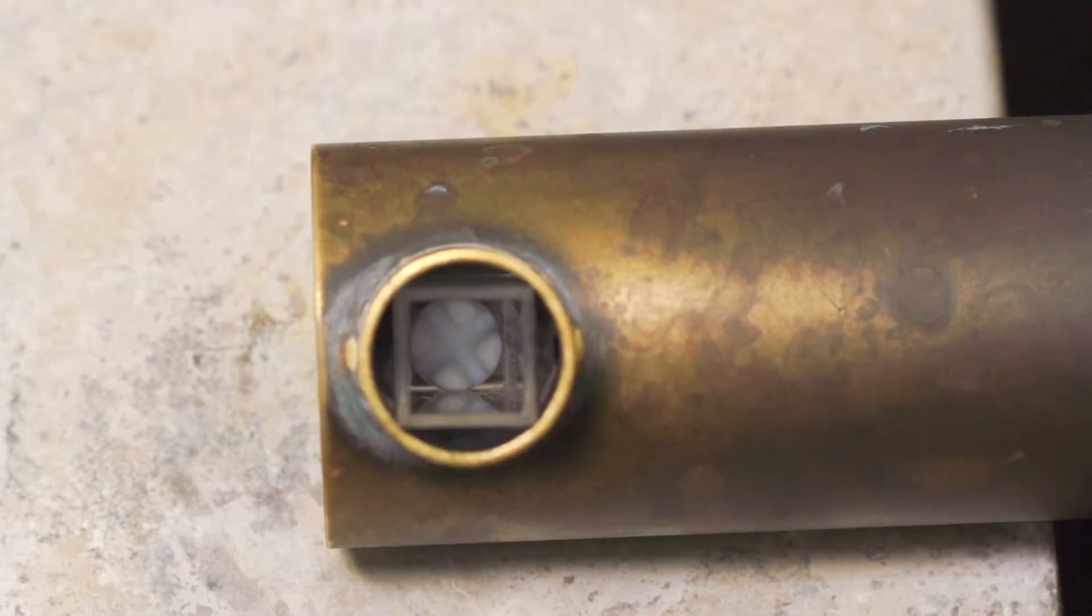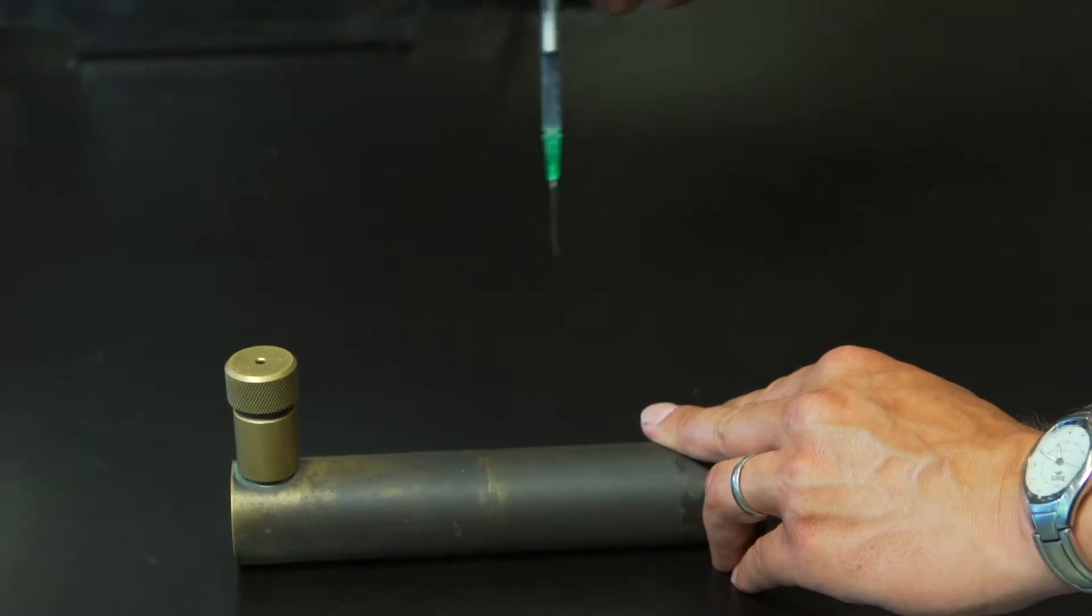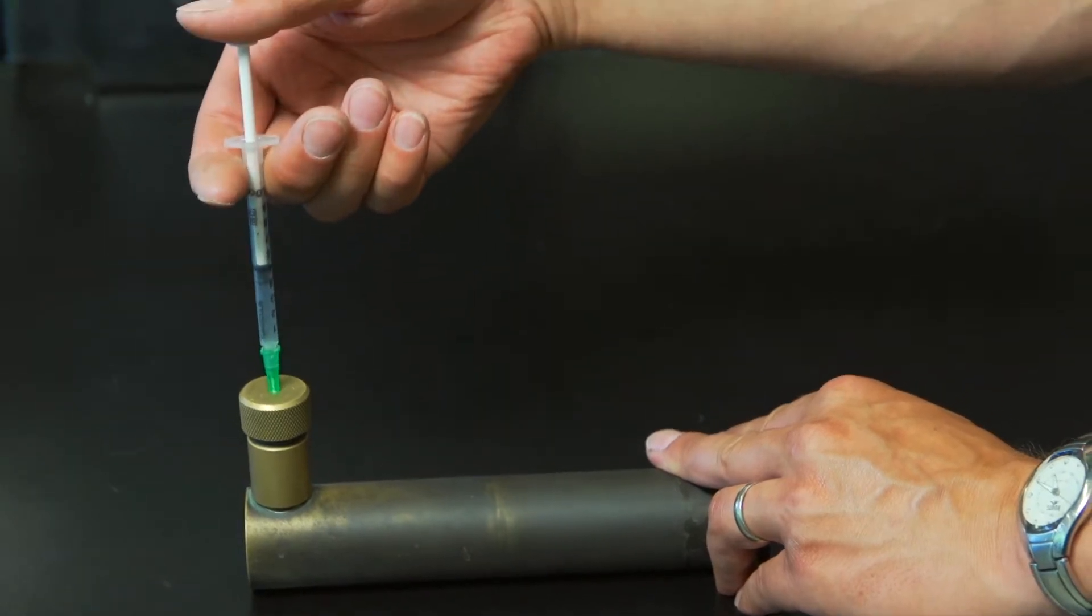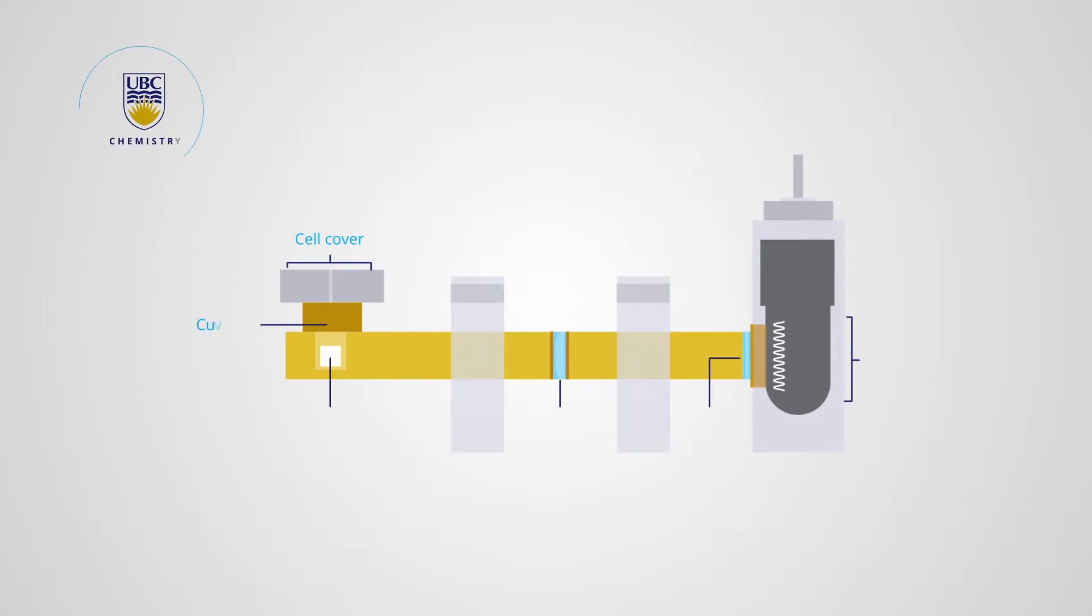Two of the three reagents, hydrogen peroxide and luminol, are pre-mixed here. Your sample is injected into the cuvette through this small opening in the cover.